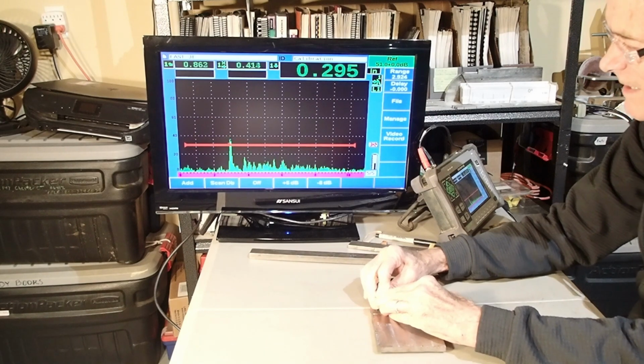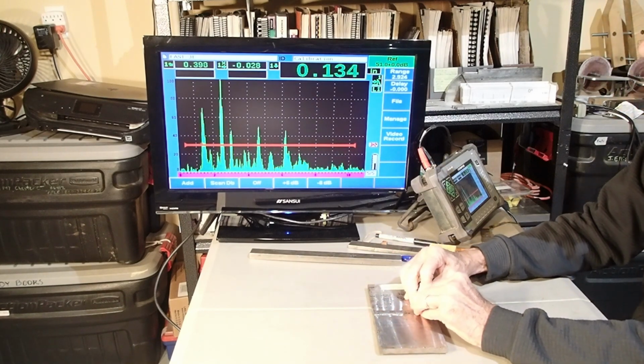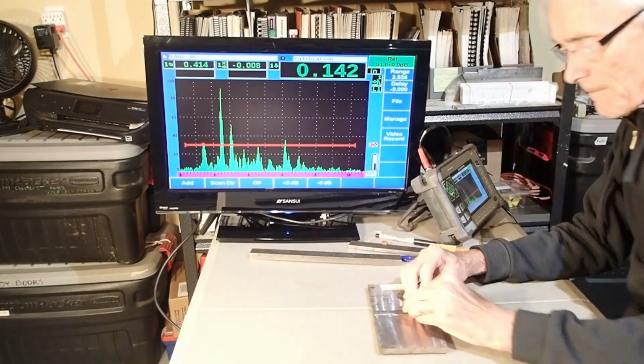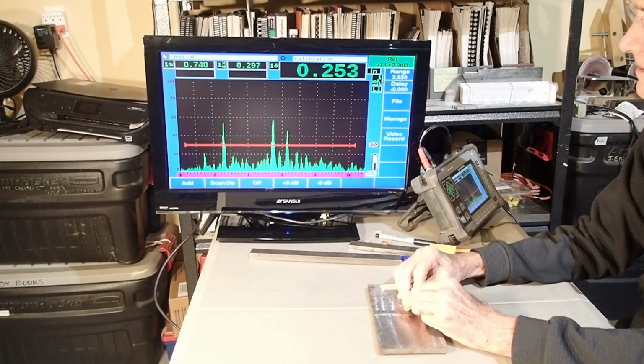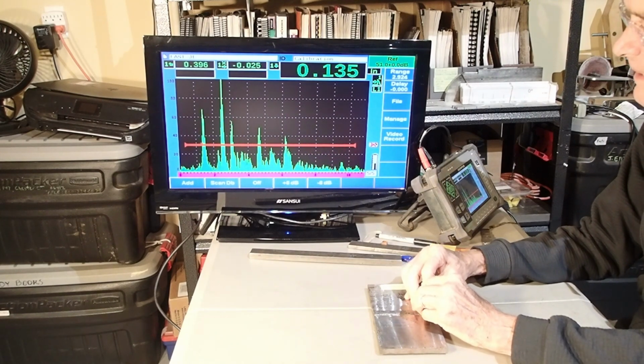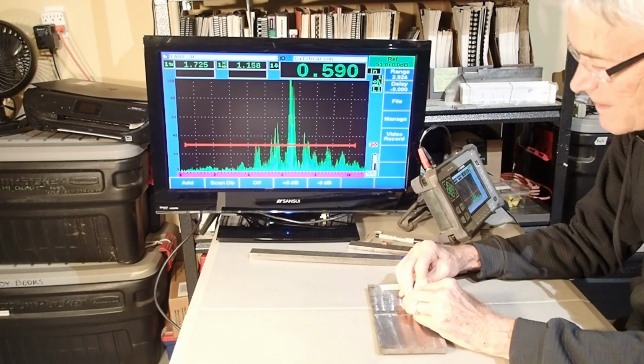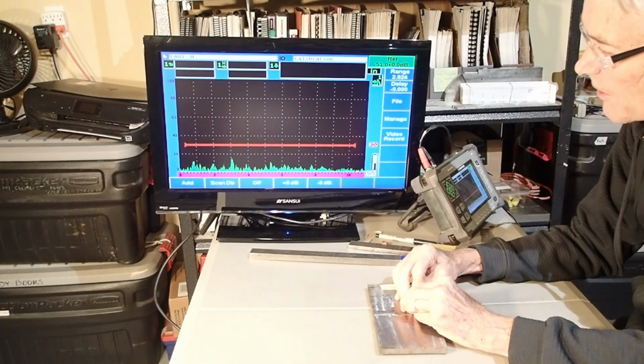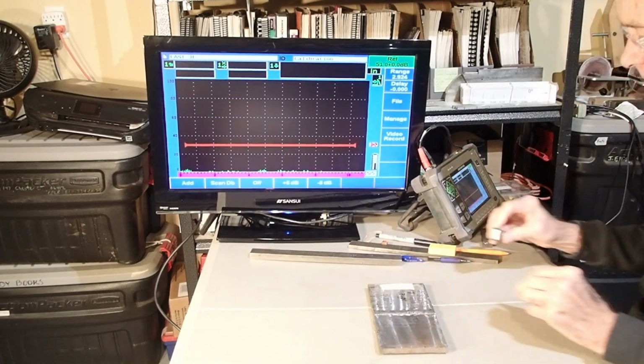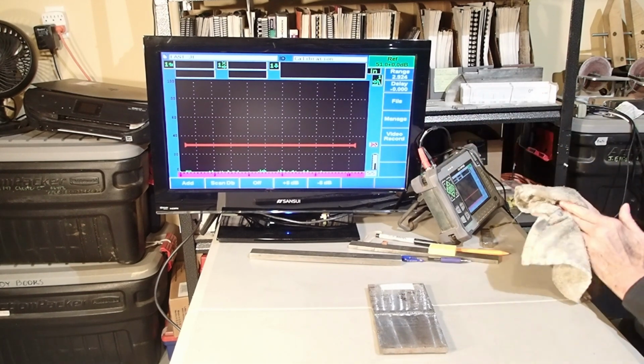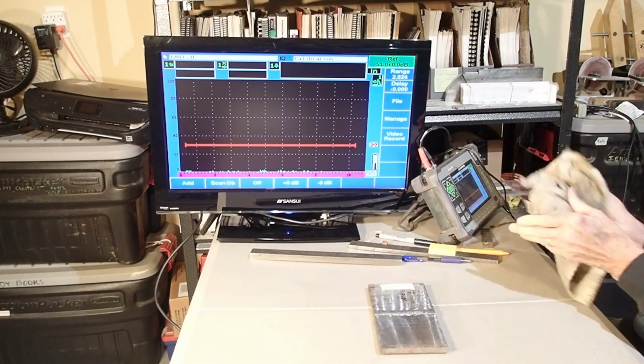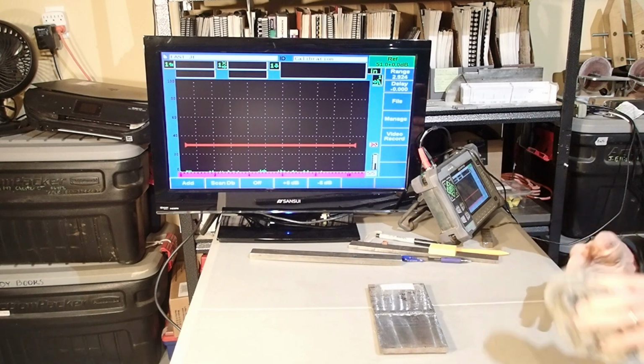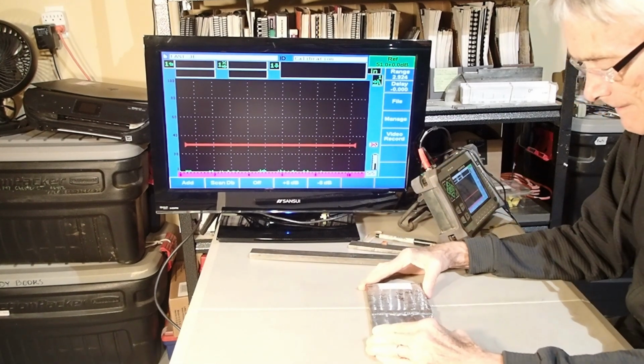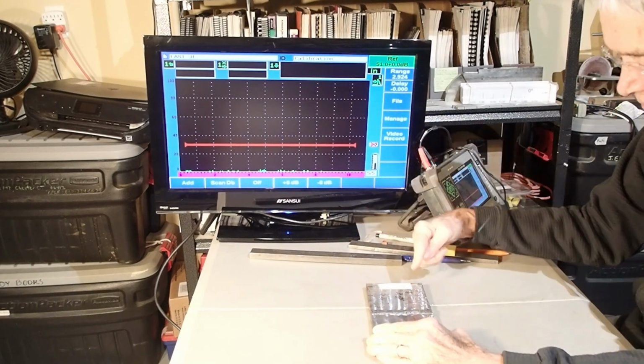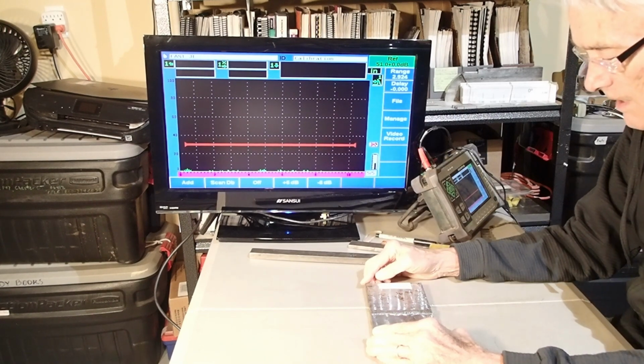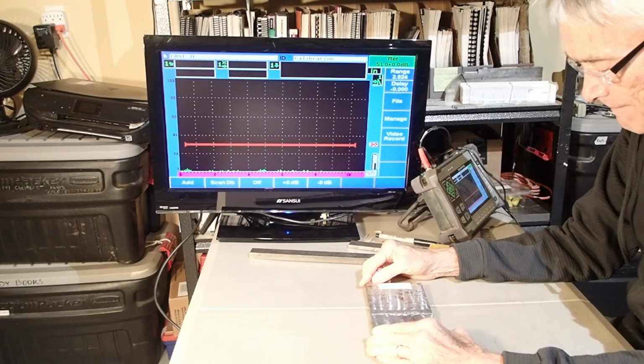But right here at the fast, this gave us a quick tip-off right away. This signal out here, that's looking like something near the OD. As close as we can get to it, jammed right up to the weld toe. Alright, so that looks like an OD weld toe crack right there. If it is an OD toe crack, we should be able to bounce into that at the end of the second leg with a 45.